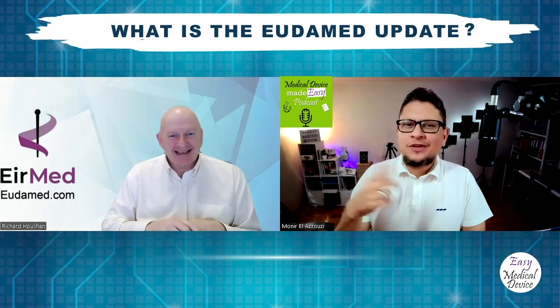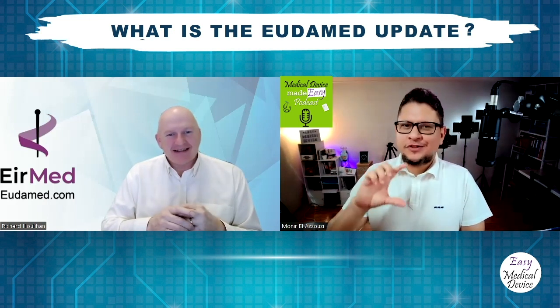But we have also the second part. When we are registering on the EUDAMED database, they first send an email to us as authorized representative if the manufacturer is located outside of Europe. They ask, is it really your customer, are you really authorized representative to them? Then we go to our account in EUDAMED and say yes, and then they send that to the member states, so Belgium or French authority or whatever, and then the authorities have to review and approve and give you the SRN number.